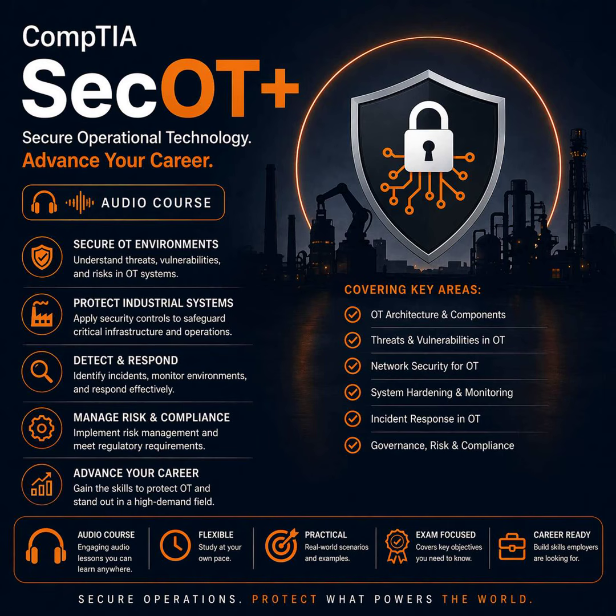A common beginner misunderstanding is treating interoperability as an unqualified good, assuming that more connectivity automatically means better operations. In reality, more connectivity can increase complexity, and complexity can create more failure points and more security exposure. Another misunderstanding is assuming that OPC UA automatically makes everything safe, when it actually provides capabilities that must be correctly used and maintained. Beginners also sometimes assume that if the data is being displayed, it must be correct, but display correctness depends on correct tag mapping, correct refresh behavior, and correct trust in the source.